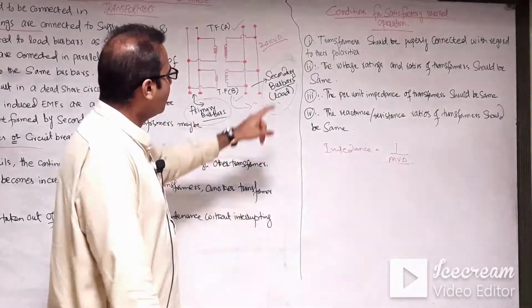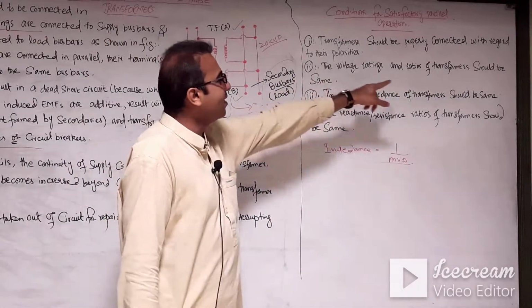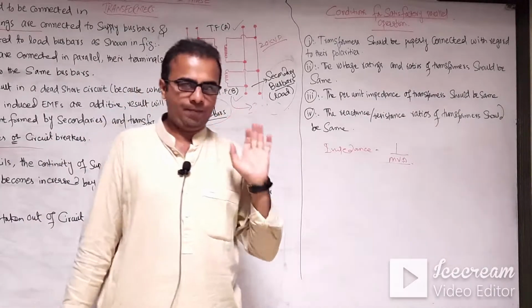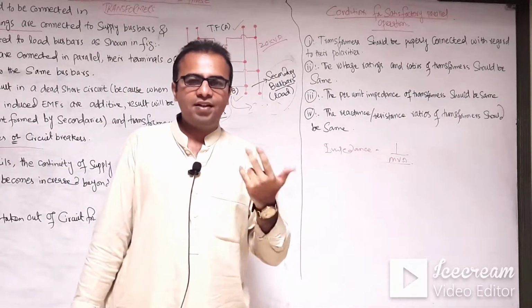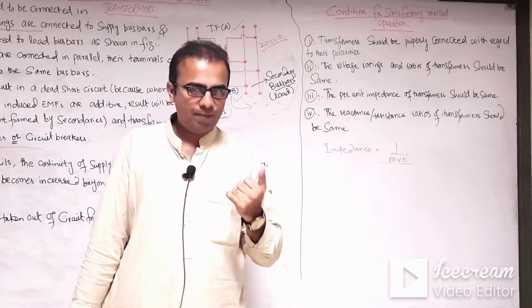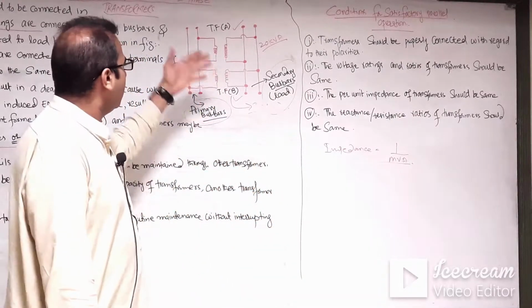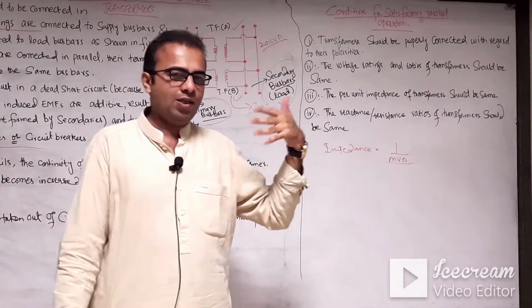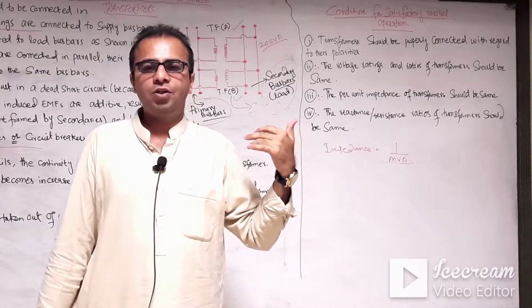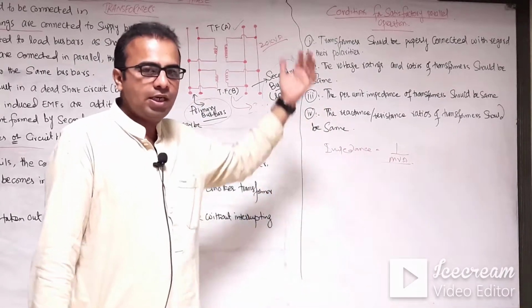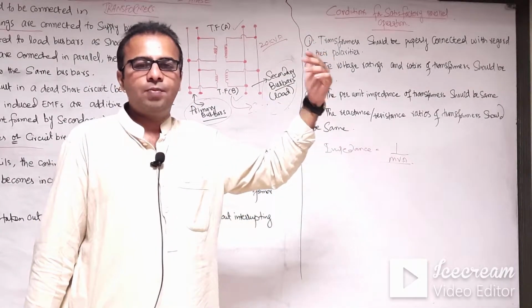Second is that the voltage ratings and the ratios of the transformers should be the same. The voltage ratings mean the primary side voltages and the secondary side voltages of both transformers should be the same, and their voltage ratio, meaning induced EMF, should be the same.